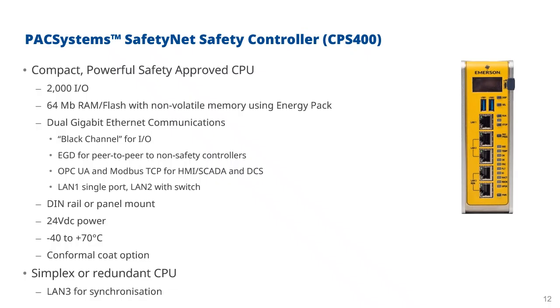On the CPU side, the architecture is built around either a simplex or redundant CPU. From the SIL 2 certification point of view, there's no difference, but having a redundant CPU gives you the capability to have slightly higher availability for the system. So with a simplex CPU, if the CPU fails, the plant trips. If you've got a redundant CPU, you've got the possibility to have one CPU fail or be turned off for maintenance, and the other CPU can carry on running the safety function. So it gives you higher availability without affecting the safety function.